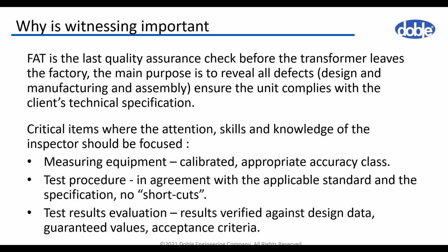It is very important that the equipment used during this test is calibrated, and also that the equipment is suitable for the test we perform, with the appropriate accuracy class. Test procedures, or how the tests are performed. This is maybe the most critical part of the FAT. This is something we observe in great detail.